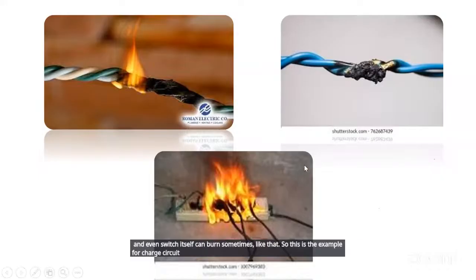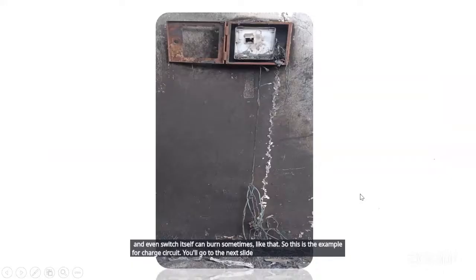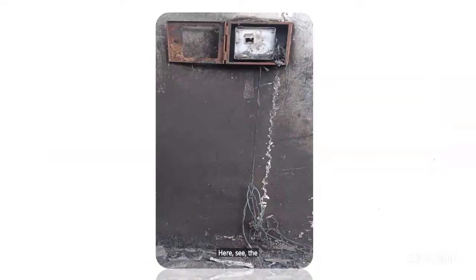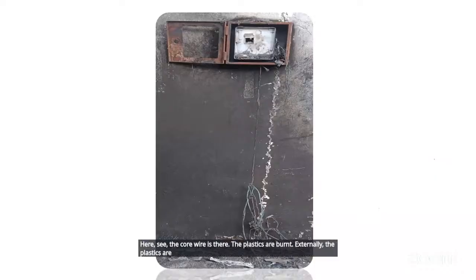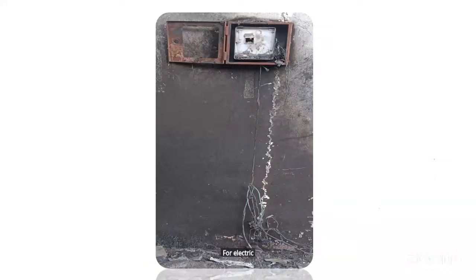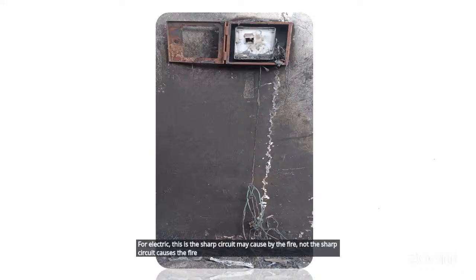Go to the next slide. Here see, the core wire is there, and the plastics are burnt externally, not internally. Heat externally affected the cable, and the cable insulation got burnt. So this is not caused by the electricity. Here the short circuit may have been caused by the fire; the short circuit did not cause the fire. We have to understand the difference between a fire caused by a short circuit and a short circuit caused by fire. Next, please.